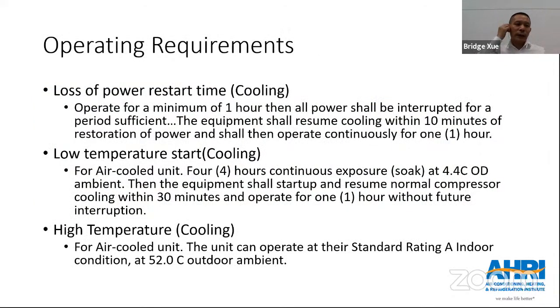So last slide, this is additional requirement for the equipment which will be used for the testing. We need to make sure the unit can be operated safely and continuously. So the first one is loss of power restart timing. This will be applied for cooling: operate for a minimum of 1 hour, then all power shall be interrupted for a short time.